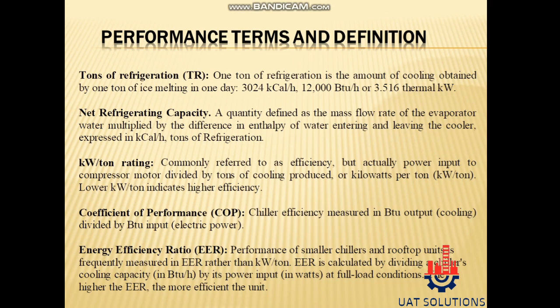Energy efficiency ratio (EER): performance of smaller chillers and rooftop units is frequently measured in EER rather than KW/tonne. EER is calculated by dividing a chiller's cooling capacity in BTU by its power input in watts at full load conditions. The higher the EER, the more efficient the unit.